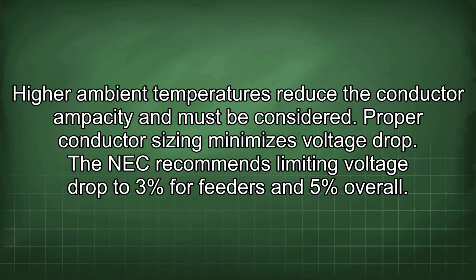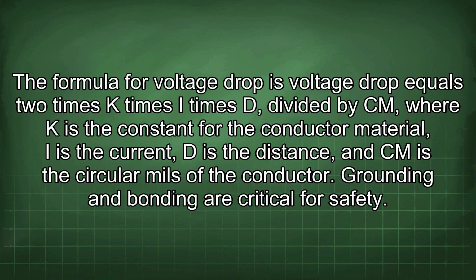Proper conductor sizing minimizes voltage drop. The NEC recommends limiting voltage drop to 3% for feeders and 5% overall. The formula for voltage drop is voltage drop equals 2 times K times I times D divided by CM, where K is the constant for the conductor material, I is the current, D is the distance, and CM is the circular mils of the conductor.